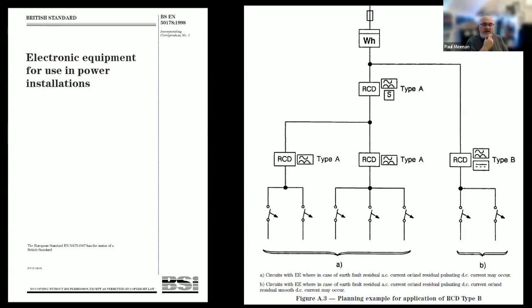BS EN 50178 in 1998 clearly showed that if you had something where DC pulsating current could occur, you would configure the installation in your board separately. So you've got type A RCDs protecting circuits, a time delayed RCD to ensure you have selectivity, but then separate to that, a type B, which gives you more immunity to DC. And if there was leakage, it wouldn't saturate or blind the type A. So this is what I keep saying to people: configuration is key. Configuration of your protective devices, configuration of your earthing is incredibly important.